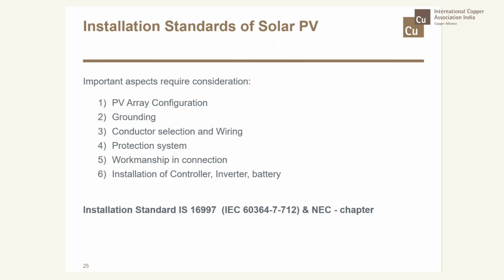Termination of cables is very important, as voltage drop due to bad termination can affect the performance of the whole system very badly. Installation of the controller and atmospheric conditioning have to be managed along with the inverter and battery. That would require expert handling, which I am sure will be covered in detail in the next presentations. So standard IEC 60364-7-712 has been adopted as Indian standard IS 16997, which should be used. A new chapter in the National Electric Code of India on this topic has also been added. This NEC is under revision, and the draft NEC is now available on the BIS website for public comments. All can look into it and send comments to BIS.